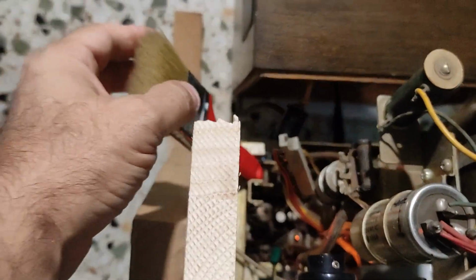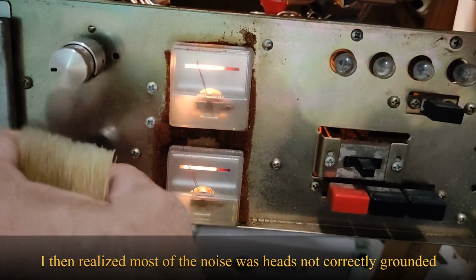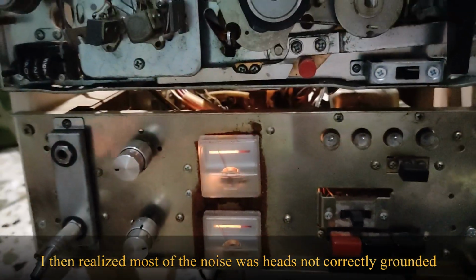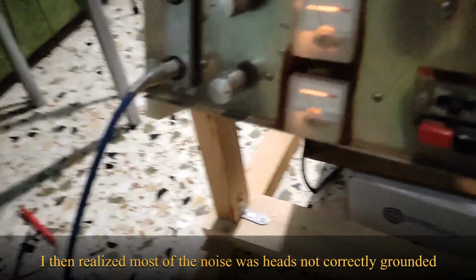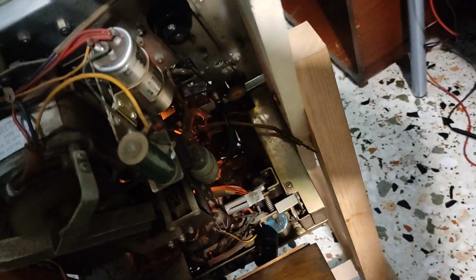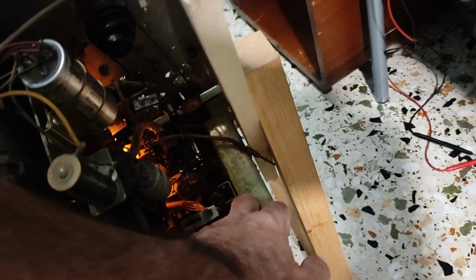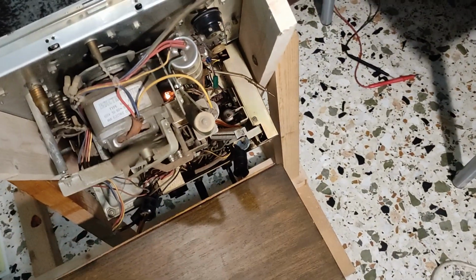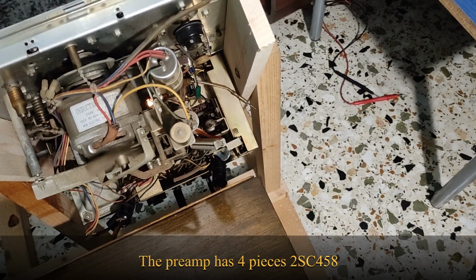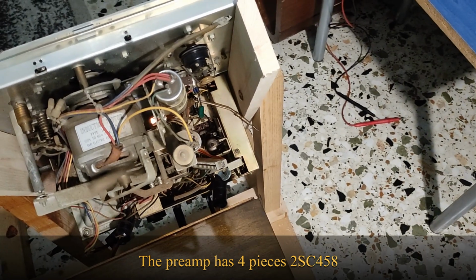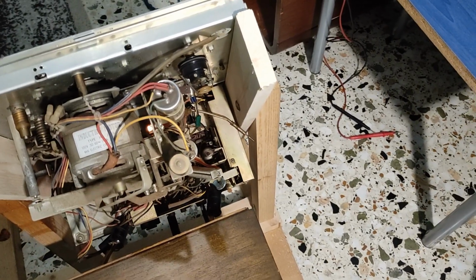So, this is with the preamplifiers, but if I take out this thing for the record switch, like that, now we have a lot of noise on both channels. So I have to investigate what's going on with the noise. The preamplifier of this machine is in here. So if the machine is on this frame, I cannot open the preamplifier which is here. I have to take out the lower part and check the preamplifier. I will see if I will change the transistors. They are the notorious 458s, which go bad nearly all the time. So I might replace the transistors, and I will see if I have any problematic capacitors. I have bought all of them.